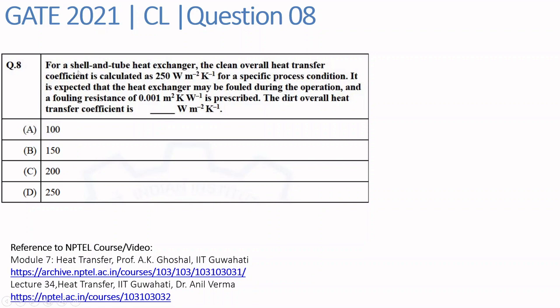The question is, for a shell and tube heat exchanger, the clean overall heat transfer coefficient is calculated as 250 watt per meter square Kelvin for a specific process condition. It is expected that the heat exchanger may be fouled during operation, and the fouling resistance of 0.001 meter square Kelvin per watt is prescribed. The dirt overall heat transfer coefficient is to be found, in watt per meter square per Kelvin.